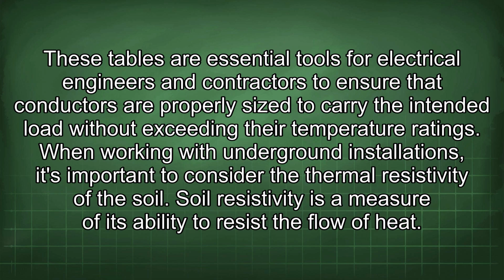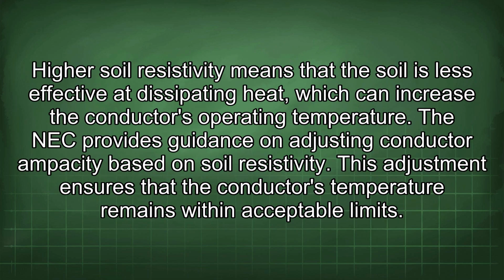When working with underground installations, it's important to consider the thermal resistivity of the soil. Soil resistivity is a measure of its ability to resist the flow of heat. Higher soil resistivity means that the soil is less effective at dissipating heat, which can increase the conductor's operating temperature. The NEC provides guidance on adjusting conductor ampacity based on soil resistivity. This adjustment ensures that the conductor's temperature remains within acceptable limits.